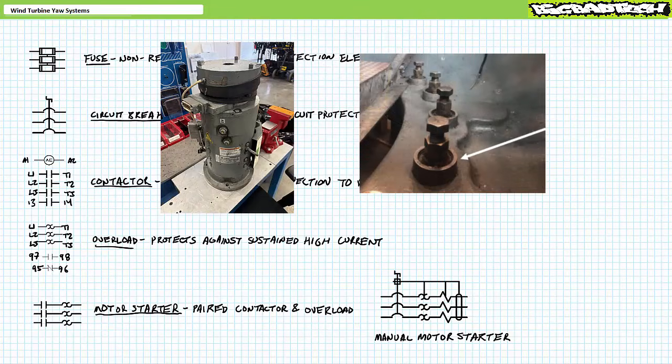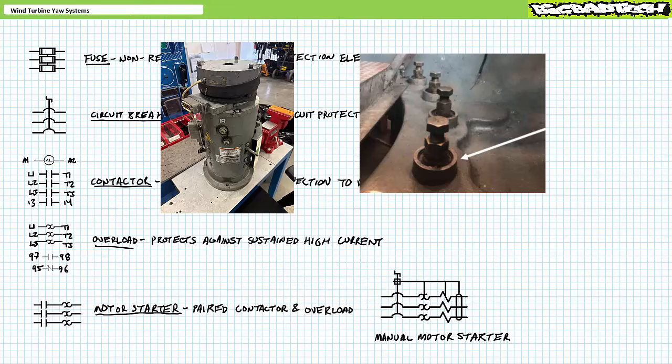Lastly, since some yaw systems do not warrant the inclusion of hydraulic brakes, I should mention that there exist spring-applied electric release friction brakes that are sometimes mounted right on the motor or alternately on the nacelle frame. You'll recall we examined spring-applied electro-release friction brakes extensively in the motor control playlist. You may see the brake coil of these devices illustrated in the primary schematic of some wind turbine systems. This particular lecture presumes the turbine is making use of hydraulic brakes.